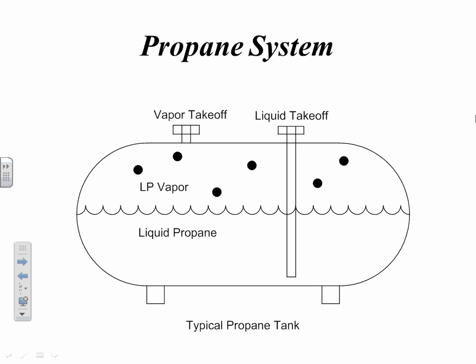And what happens in rare instances, if we had a vapor takeoff only, we can get vapor and liquid out of the same tank, okay? It's just how we take the fuel off. So if we look at the liquid level in the tank, there's a vapor level above it. On those extremely cold days where the wind is whipping, if we had a vapor takeoff, we may or may not be able to vaporize enough fuel to run that generator set.